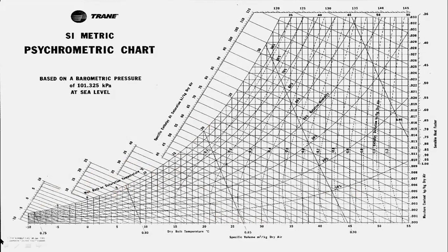The horizontal lines here you can see are shown on this y-axis scale. It shows the moisture content, kg per kg of dry air. And visually towards this line, here we will get the dew point temperature. And these lines which make a 30-degree angle with the x-axis, if we extend this line up to this scale, it will show the specific enthalpy at saturation, kilojoule per kg of dry air.